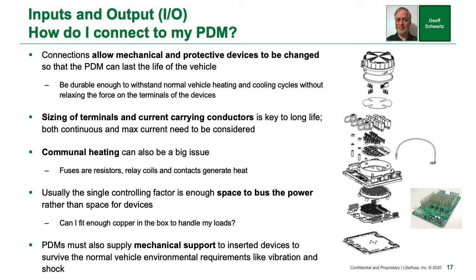But the single biggest factor inside a PDM is the space needed to bus power around, not the space for devices. Usually you can cram more devices in there physically than you can move power around for. Can I fit enough copper in my box to handle my loads?